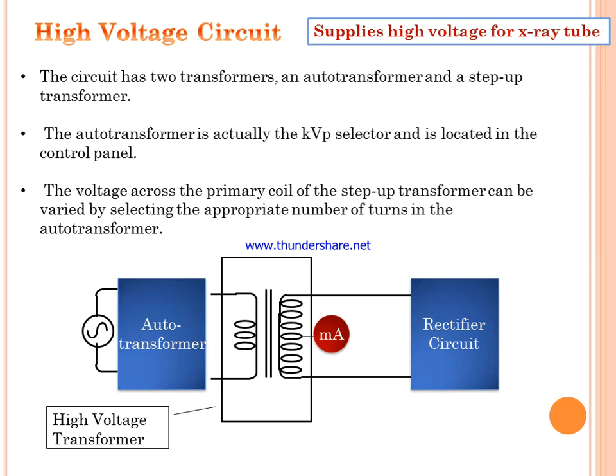The high voltage circuit supplies high voltage to the X-ray tube. It has two transformers: the auto transformer, which acts as the kVp selector located in the control panel, and the step-up transformer. The voltage across the primary coil of the step-up transformer can be varied by selecting the appropriate number of turns in the auto transformer.